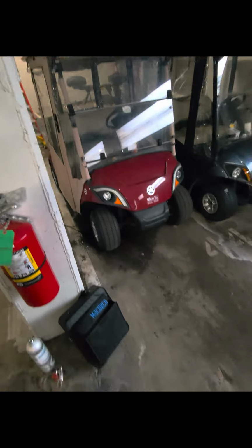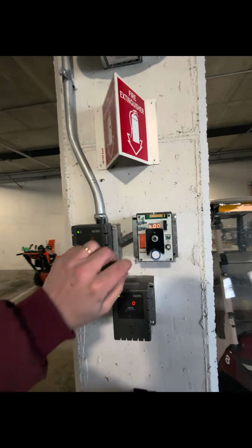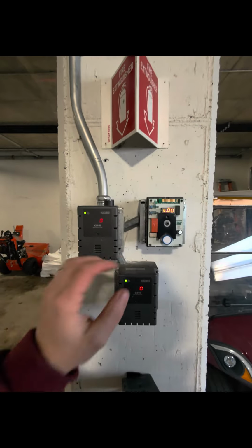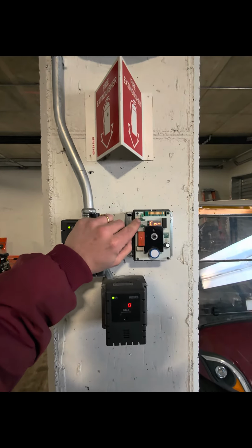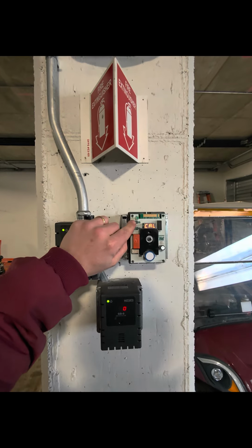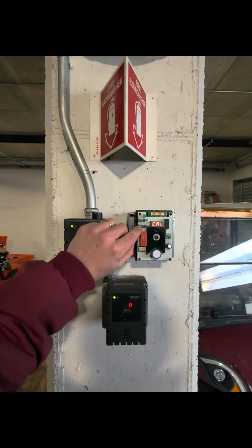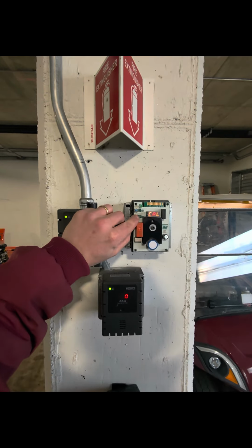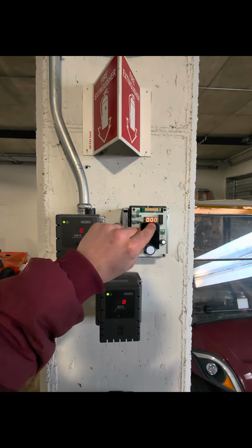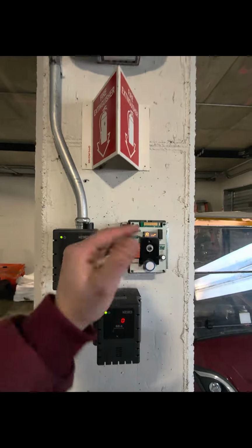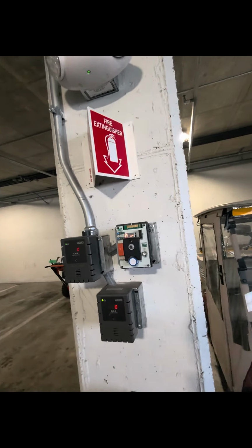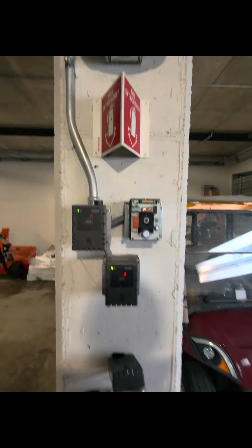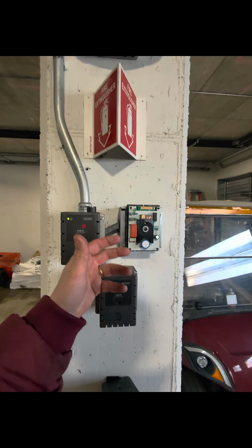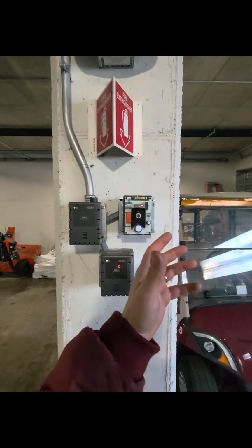So let's go. All right, so it's been long enough, so we're going to start the calibration process on this device. First thing you want to do is reset the levels to zero it out. So you go to calibration, enter, and then press enter again when you see the zeros. It's going to sample the air, and now what we're looking for is a PAS, a pass. If it doesn't pass and it fails, just run it through again.